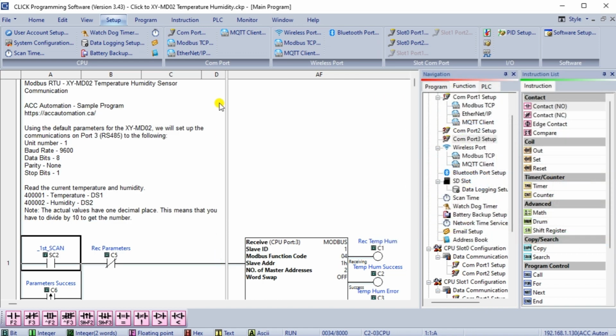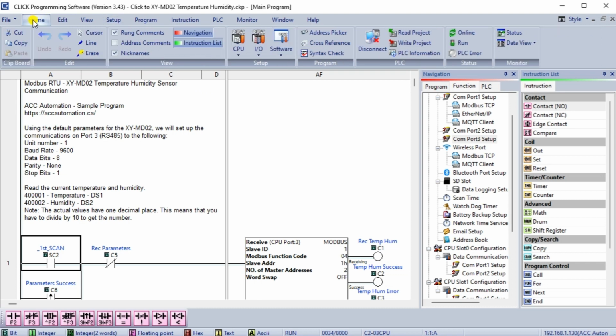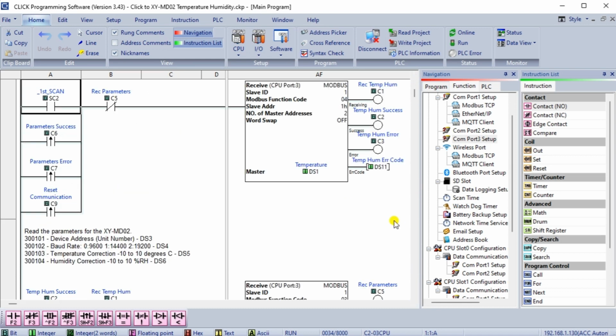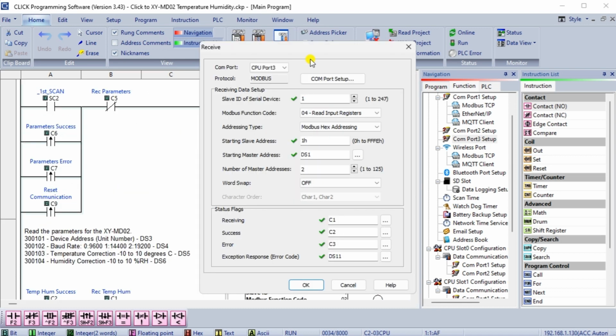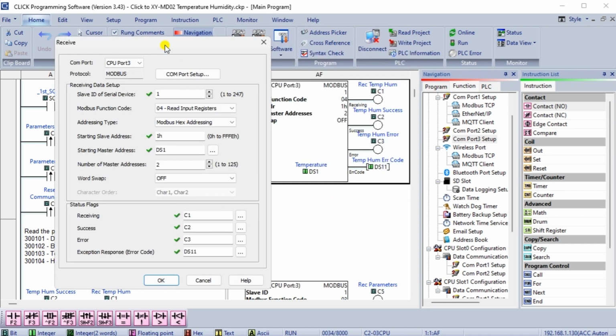We will be using 2 receive Click PLC instructions. One is to get the current temperature and humidity, and the other is to get the parameters from the sensor. Here's our first Modbus instruction that will receive data for the temperature and humidity. The slave or server of the sensor is 1. This is the default for the XY-MD02. Function code 04 read input registers is used at Modbus hex address 1. We will read 2 registers and place them in the Click PLC memory starting at DS1.